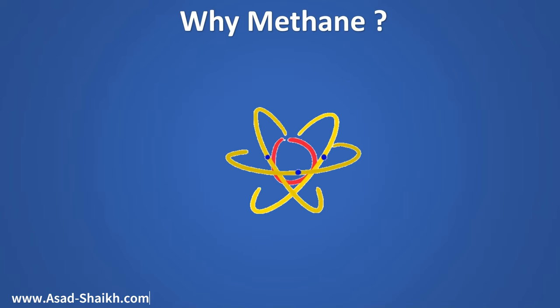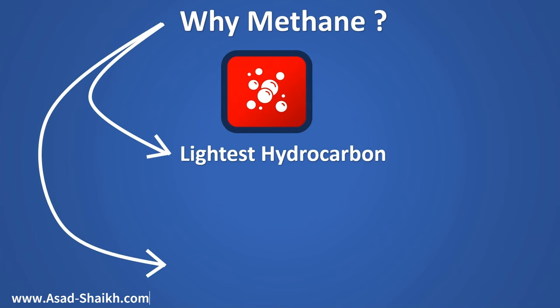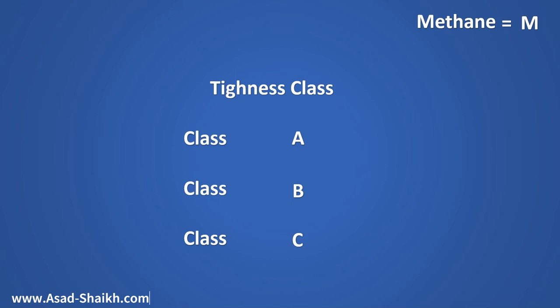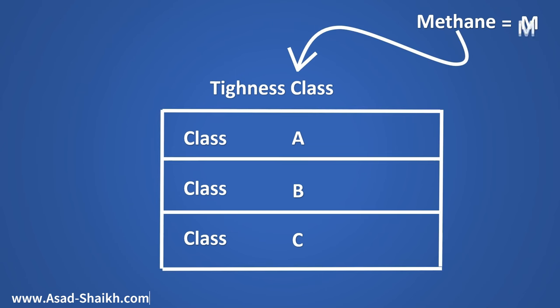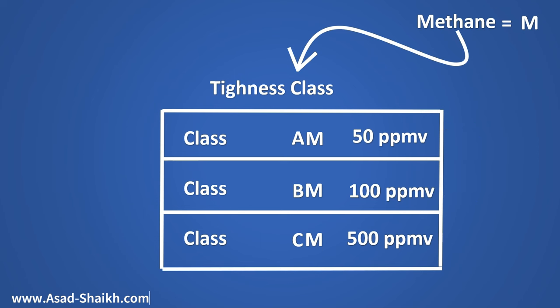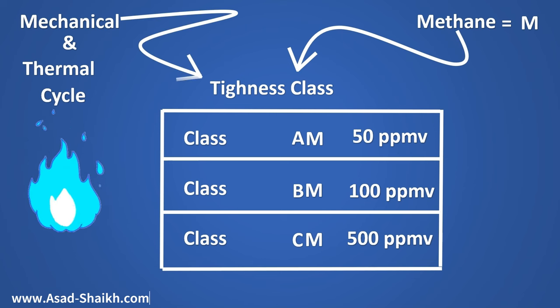Why is methane used as a test gas? Helium is understood as an inert gas, but methane is used because it is the lightest hydrocarbon, and one of the most fugitive-emission-prone industries is the hydrocarbon industry. If you can contain the lightest hydrocarbon, the other heavier gases can also be contained. Taking a practical example with methane as the test gas: the tightness requirement starts at 500 ppmv for Class C, then 100 ppmv for Class B, and finally Class A has the most stringent requirement of 50 ppmv. This testing must also be done through various mechanical cycles of on/off and thermal cycles of heating and cooling. After all this, your valve must maintain the required tightness class.